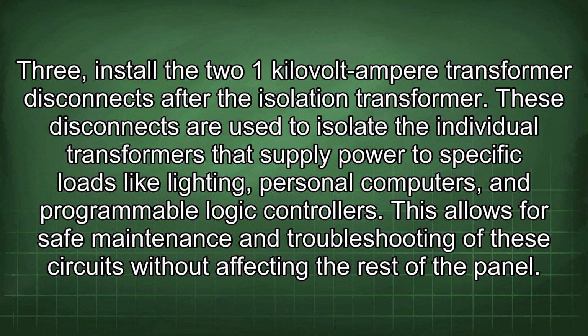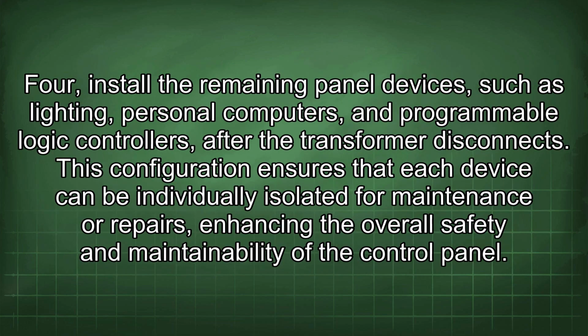3. Install the two 1 kVA transformer disconnects after the isolation transformer. These disconnects are used to isolate the individual transformers that supply power to specific loads like lighting, personal computers, and programmable logic controllers. This allows for safe maintenance and troubleshooting of these circuits without affecting the rest of the panel. 4. Install the remaining panel devices, such as lighting, personal computers, and programmable logic controllers after the transformer disconnects. This configuration ensures that each device can be individually isolated for maintenance or repairs, enhancing the overall safety and maintainability of the control panel.